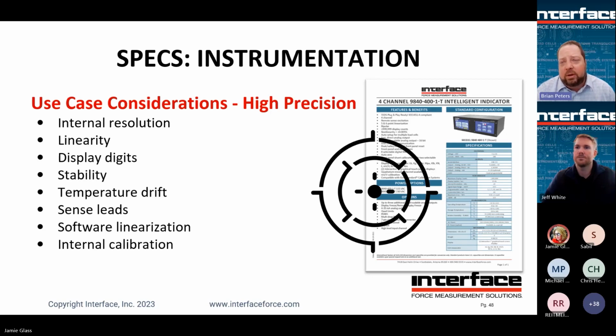Software linearization. So this is something that our gold standard software in particular does, where it'll actually take the signal straight through the device, and it will apply a polynomial equation essentially. So now you've essentially removed linearity concerns really from your sensor, because you've been able to now get such a well-defined output curve in your instrumentation. Then there's also, is it internally calibrated? Do you need to have proof? Do you need to have A2LA accredited internal calibration, millivolt per volt cal on that instrument? How much deviation might there be without that?